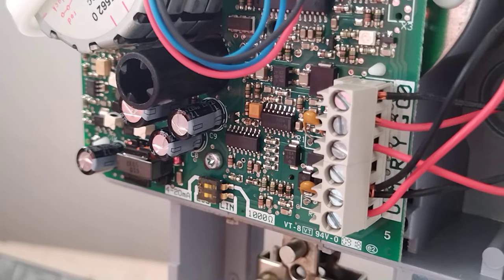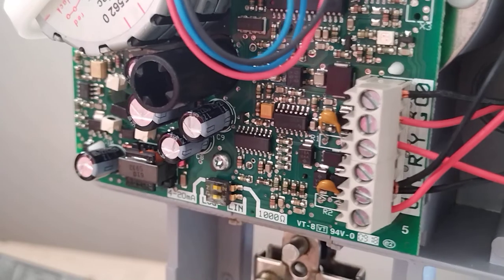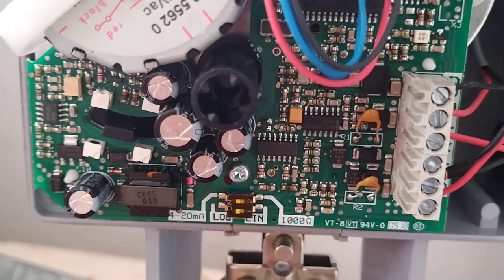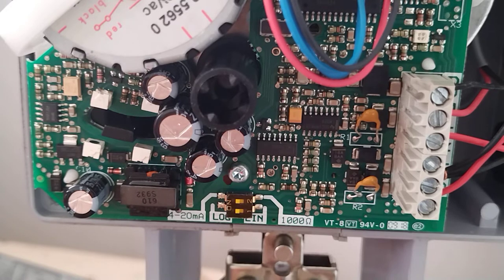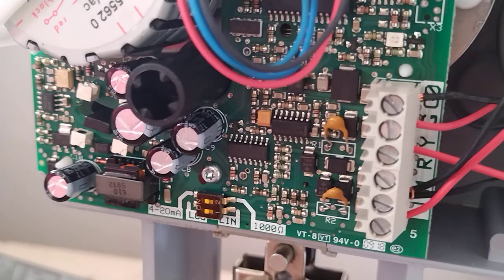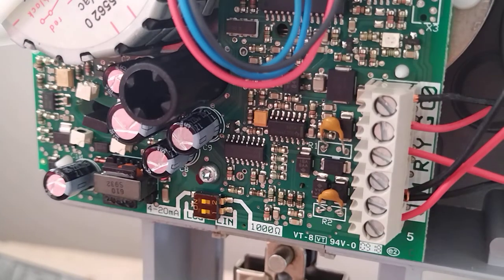As I said, when you give a control signal of 0 to 10 volts, you should also receive a feedback status. So let's say you give a 10 volts control signal, then this valve will give you also a feedback signal of 10 volts, meaning it is responding to your opening command, and it will tell our BMS, or we can display it in our BMS graphics that the valve is already opening.